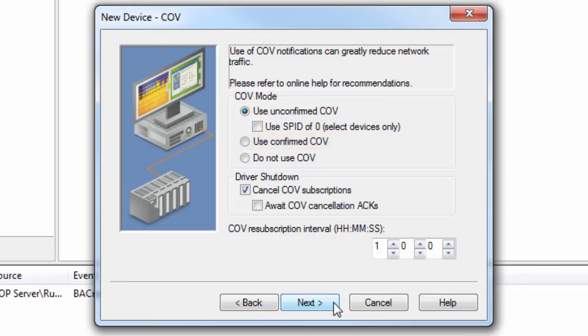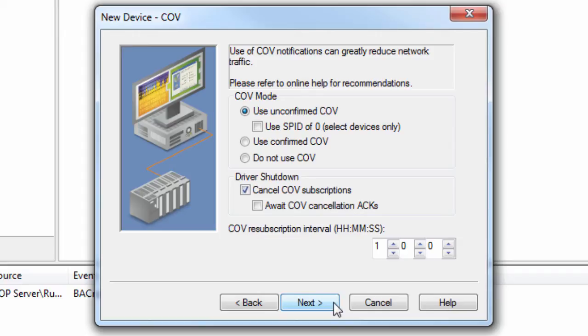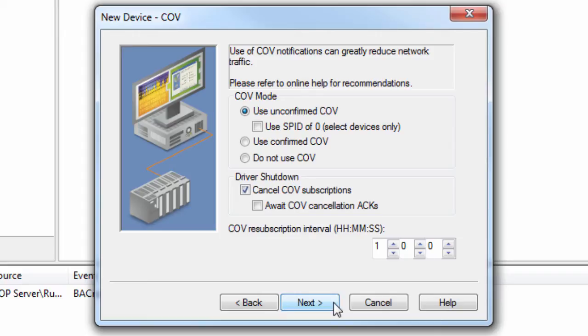Selecting Do not use COV means all of the device properties will be pulled even if the COV address modifier is present. Cancel COV subscriptions on driver shutdown tells the driver to send messages to the device on shutdown to cancel each of its COV subscriptions. Although this may slightly delay the driver shutdown, it can be important if the device has limited resources for subscriptions. Enabling Await COV Cancellation ACKs will cancel subscriptions one at a time. It will wait for the device to reply with an acknowledgement before canceling the next subscription. It also prevents the runtime from shutting down until all COV subscriptions have been cancelled. It may be helpful for a device that cannot process multiple subscription cancellations at once.